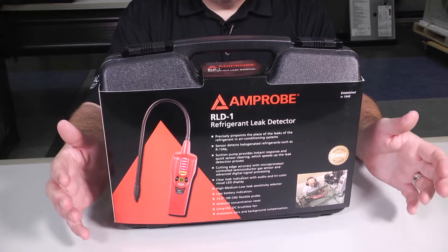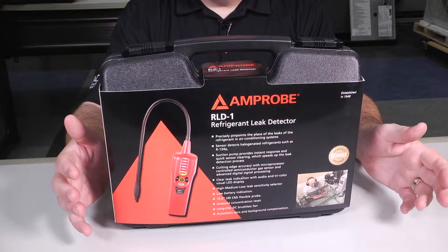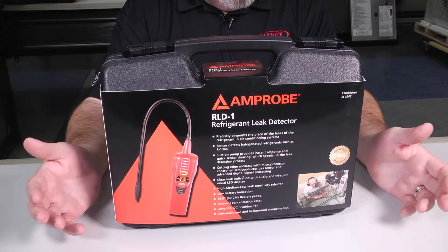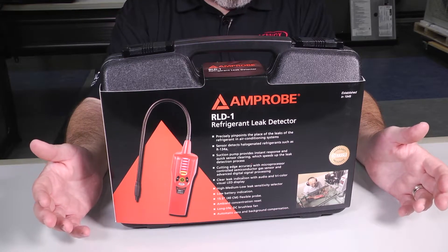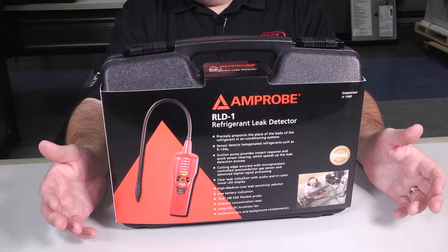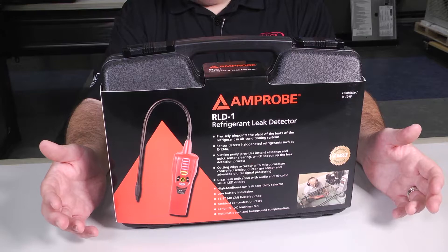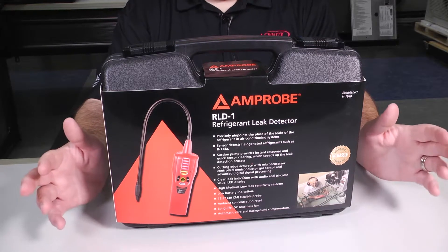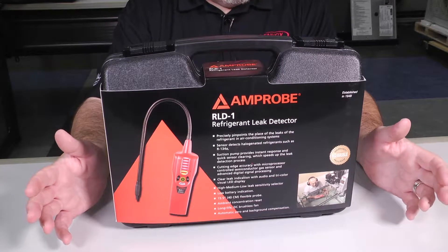What's its sensitivity? They always tell you that you should have a leak detector that can detect leaks as low as half an ounce a year. Well, when we look at this one, on the high setting it detects three grams of refrigerant leak per year. What does that come out to in ounces? That's about 0.1058 ounces — much more accurate than the industry standard we tell you to shoot for.